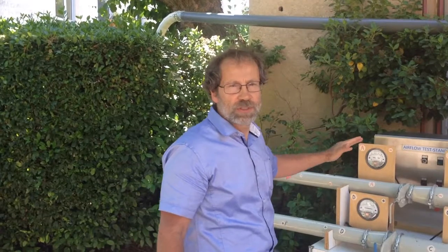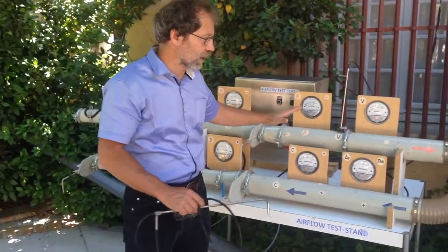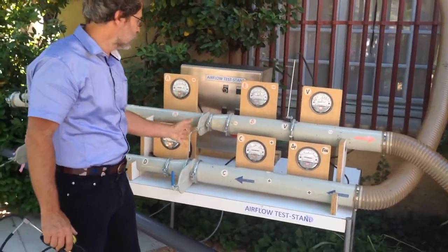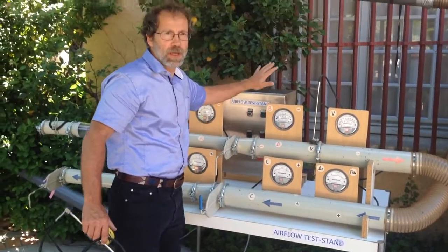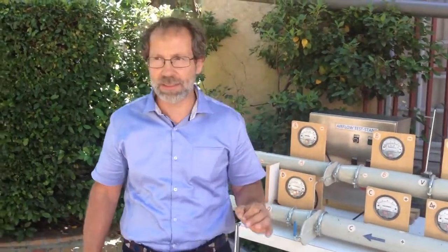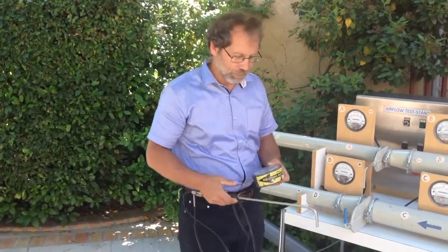So I recommend you to go out and take some old fan which is just sitting around on the shelf in your factory, take some old ductwork. This is a simple test stand. I know it's not so beautiful, but it reflects all you need. Build a simple system, change the diameters, do some slide gates in it, put a frequency inverter, and then let your operating personnel play with this. And by playing with this, doing this and that, they will understand deep down how this system works. They can verify how easy it is to use a pitot tube and static pressure measurement gauges.